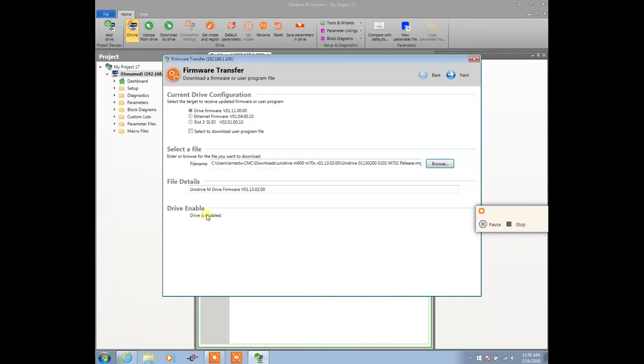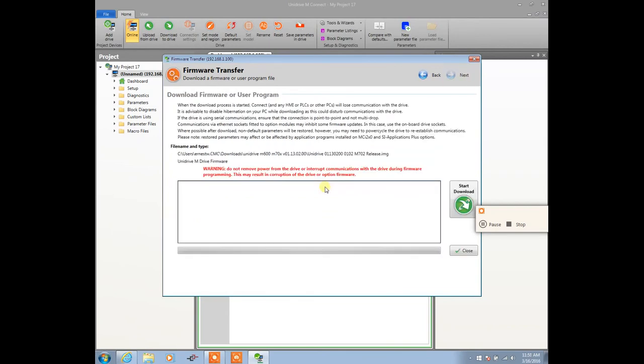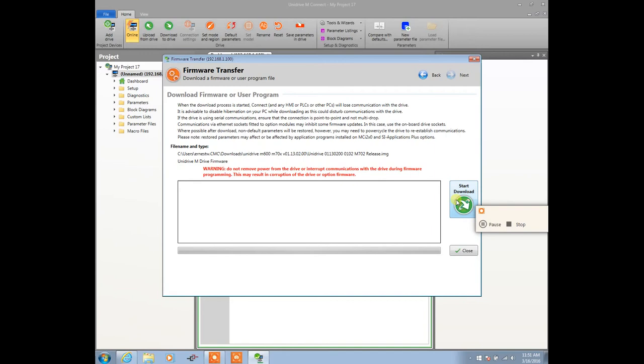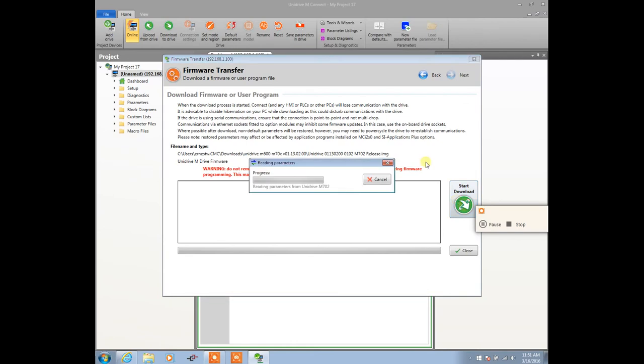Make sure the drive is disabled. This gives you the firmware information, and we will then select Next. This is going to tell us to make sure we don't lose power to the drive and that the drive is connected. Don't disconnect the Ethernet cable during the download. Just make sure everything stays as is. We're going to now hit Start Download, and our download has begun.